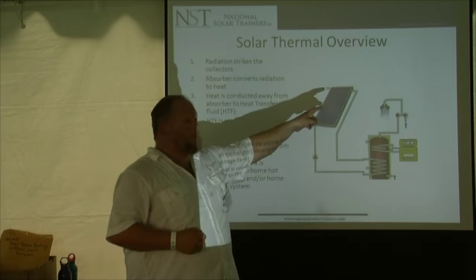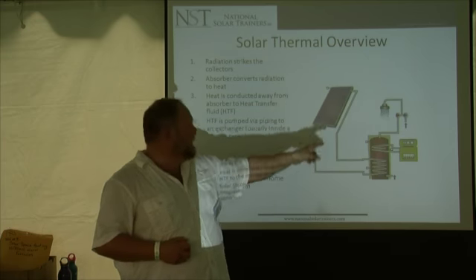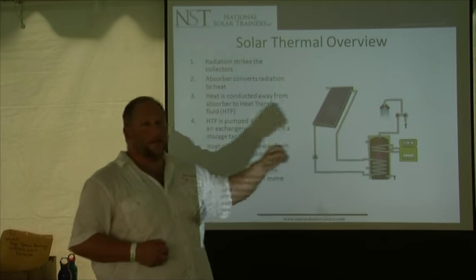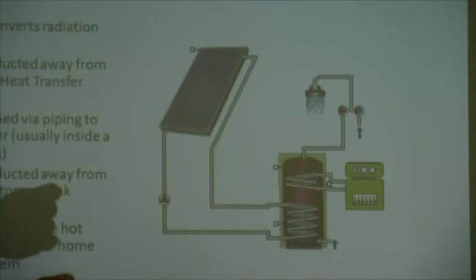There's a temperature sensor at the collectors and a temperature sensor at the tank. It's an automatic control: as soon as the collectors are hotter than the tank, the pump kicks on. When the collectors get within 3 degrees of the tank, the pump turns off. This could go on and off all day long as clouds move away and come in.